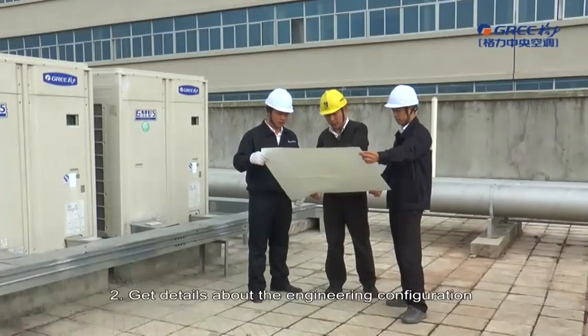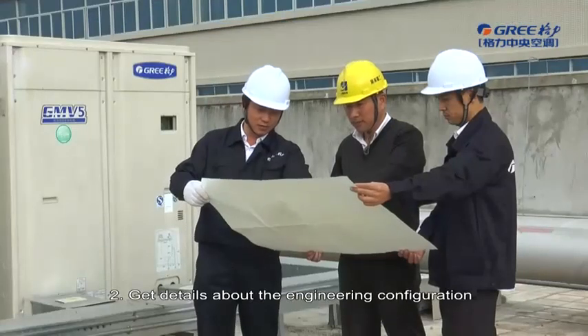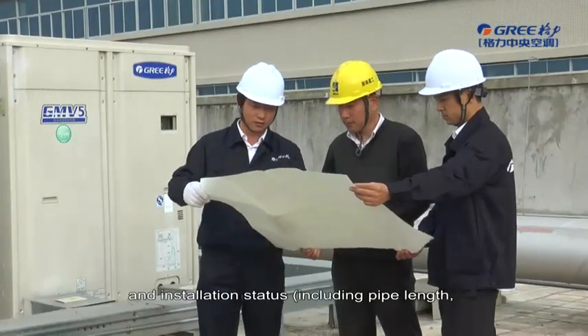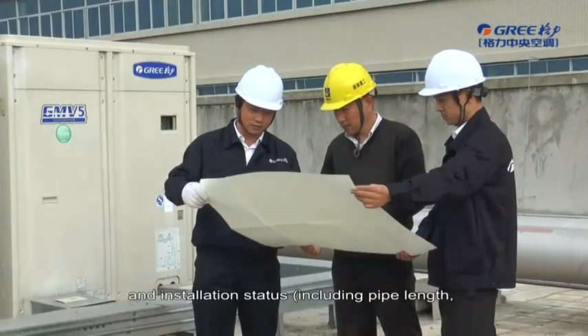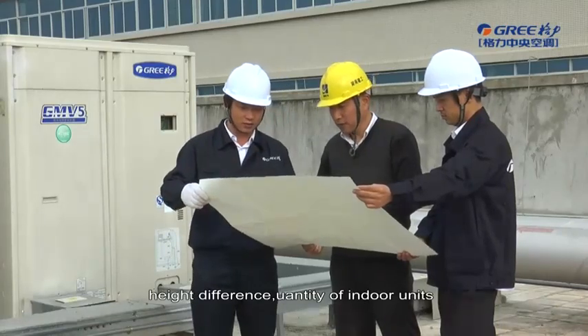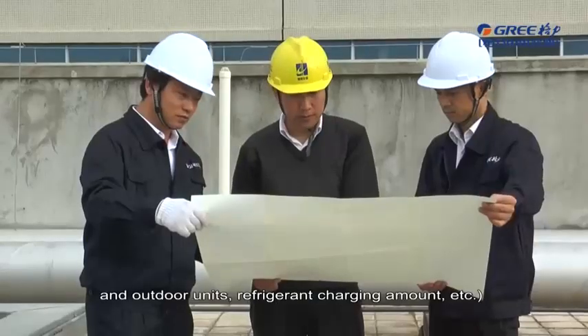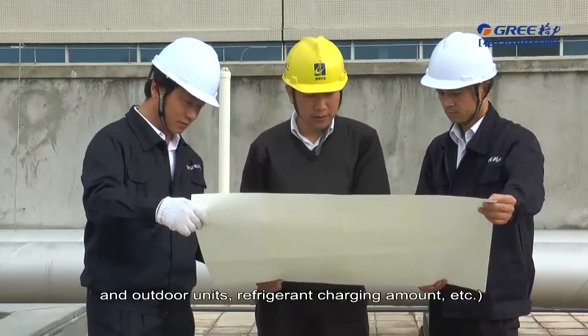Second, get details about the engineering configuration and installation status, including pipe length, height difference, quantity of indoor units and outdoor units, refrigerant charging amount, etc.